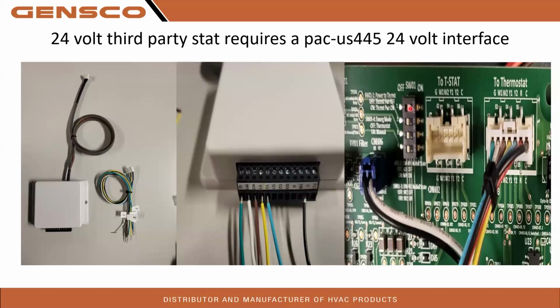This switch right here allows 24-volt transformer power from your furnace to power your TBB terminal block. So if this switch is turned off and your thermostat's not coming on, that would be why. Either you guys have to wire in your own transformer, or if the transformer in your furnace is plenty big enough, flip this switch on, you'll be good to go. Usually I'll see you guys flip this switch off and wire their own transformer if they're doing a zone system or something like that.